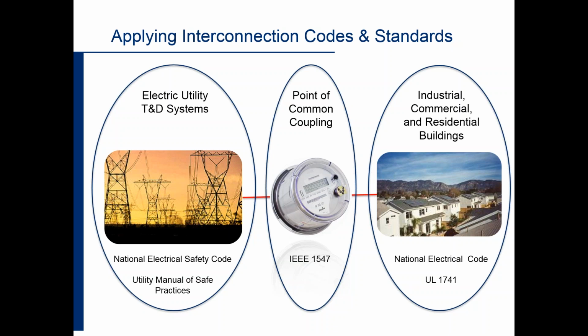It is important to have codes and standards from the utility side, the customer side, and where the two meet, or the point of common coupling. In the U.S., utility side codes include the National Electric Safety Code and the Utility Manual of Safe Practices. On the customer side, the National Electric Code and UL 1741 ensure safe installation and proper electric equipment standards. And then finally, at the point of common coupling, where the two come together, IEEE 1547 governs how DPV interacts with the electric grid. IEEE 1547 is the interconnection standard.